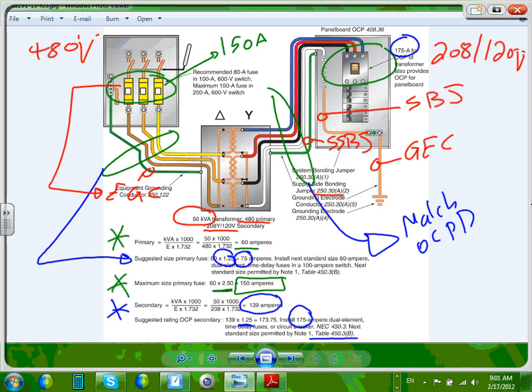For the most part, we size them based on the conductor right here. So we size this one and this one and this one. All of these, supply side bonding jumper, or system bonding jumper, main or grounding electrode conductor, based on the conductor that's coming to the panel.